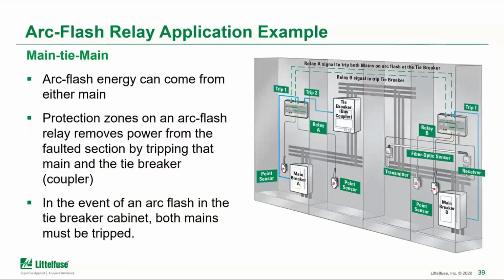And this shows how this would be configured on a typical system. Like any other protection relaying system, it can be set up with multiple zones to work with a tiebreaker application, so that if an arc is seen on one side of the bus, the light sensors can detect it, trip the local breaker or the feeder breaker for that side of the bus, as well as the tiebreaker, and allow the other side to continue operating.